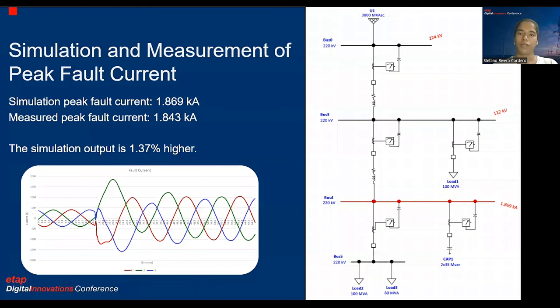Regarding the transients of the fault, the simulation showed a peak current of 1.869 kiloamps, while the measures carried out showed that the highest peak current value reached experimentally is 1.843 kiloamps. This means that in this parameter, the simulation deviates by 1.37% from the real value.